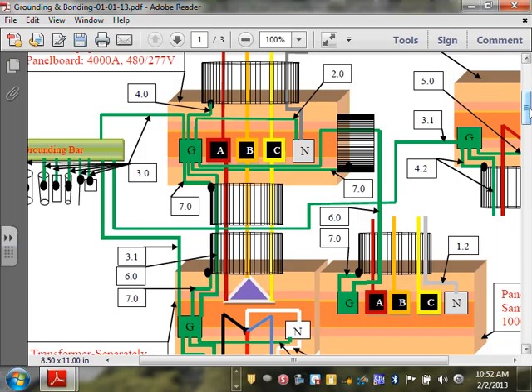Why load side? The number 4 was supply side bonding jumper. Here's the main, the conduit coming before the main, that's supply side bonding jumper. Here's the main, the conduit going after the main, that's called equipment bonding jumper load side. Why load side? Because it's the load side of the service. Does that make sense? The load side of the service.